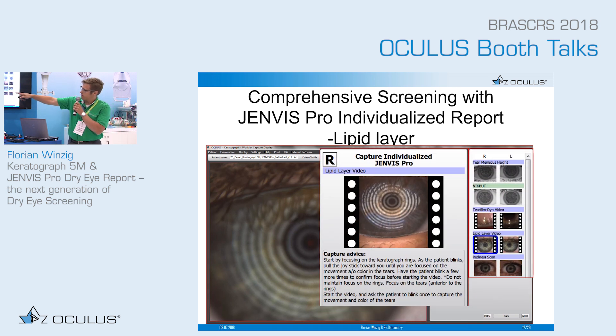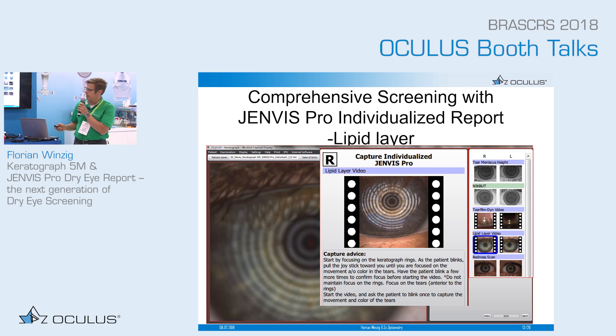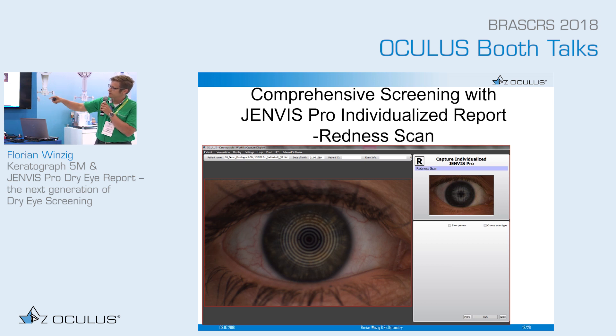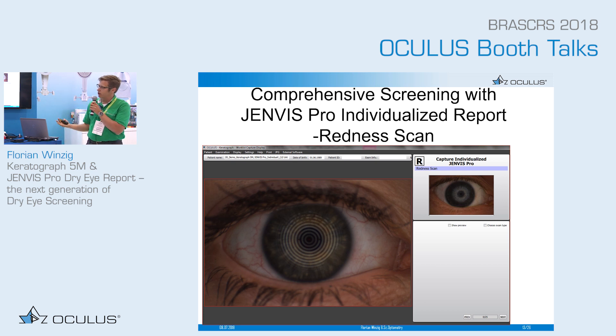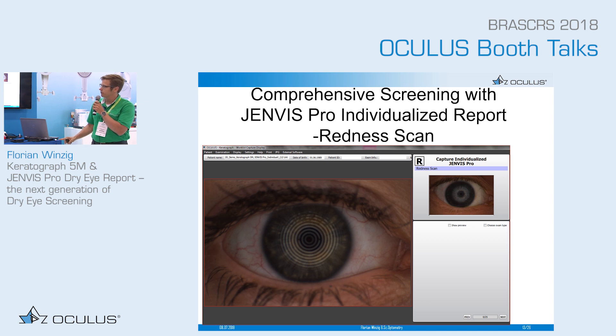Everything described is also written as instructions for the technician performing the examination process. The redness scan is also very easy to perform — you simply capture an image where the thin red vessels of the sclera are sharp, and then the software automatically calculates the ratio between the thin red vessels and the white background of the sclera.